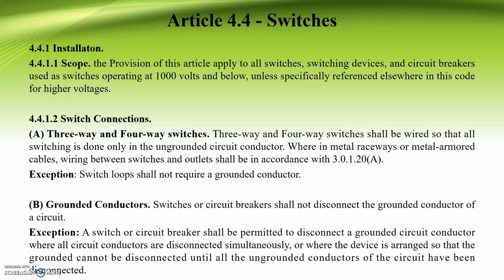So first is the 3-way and 4-way switches. So 3-way and 4-way switches shall be wired so that all switching is done only in the ungrounded circuit conductor. So where in metal raceway or metal armored cables, wiring between switches and outlets shall be in accordance with chapter 3.0.1.20a. So exception, switch loops shall not require a grounded conductor.